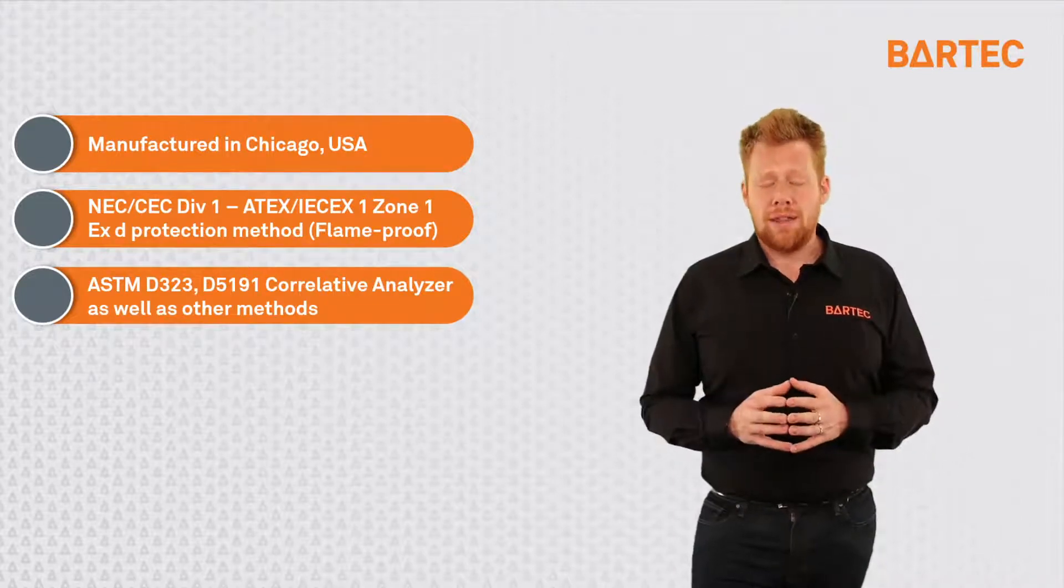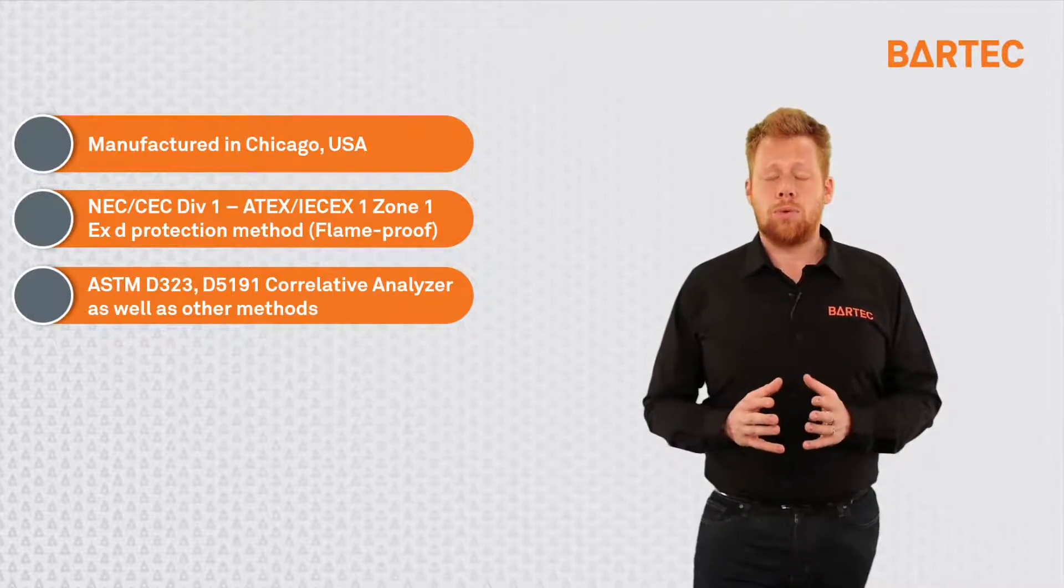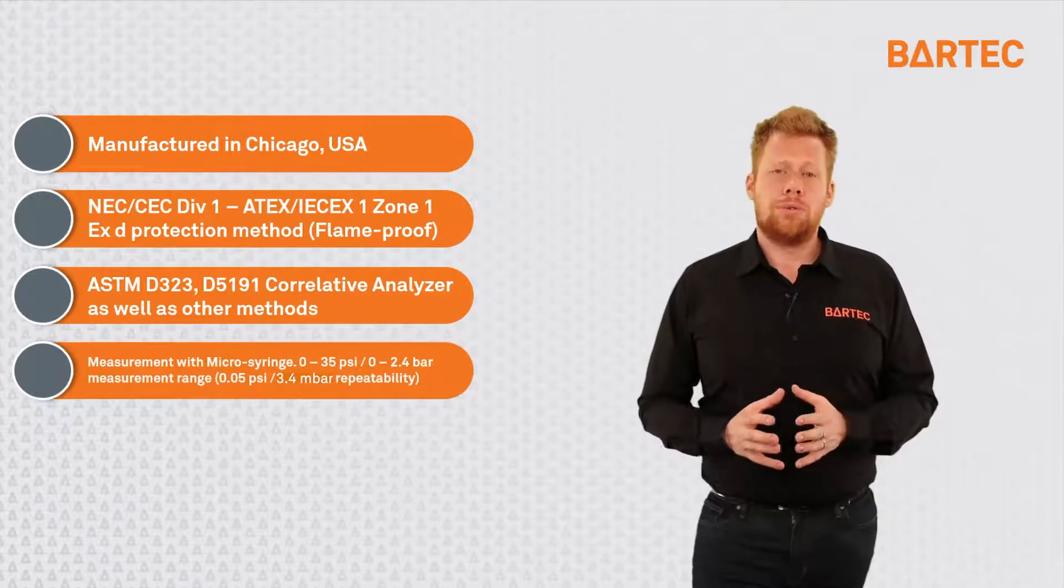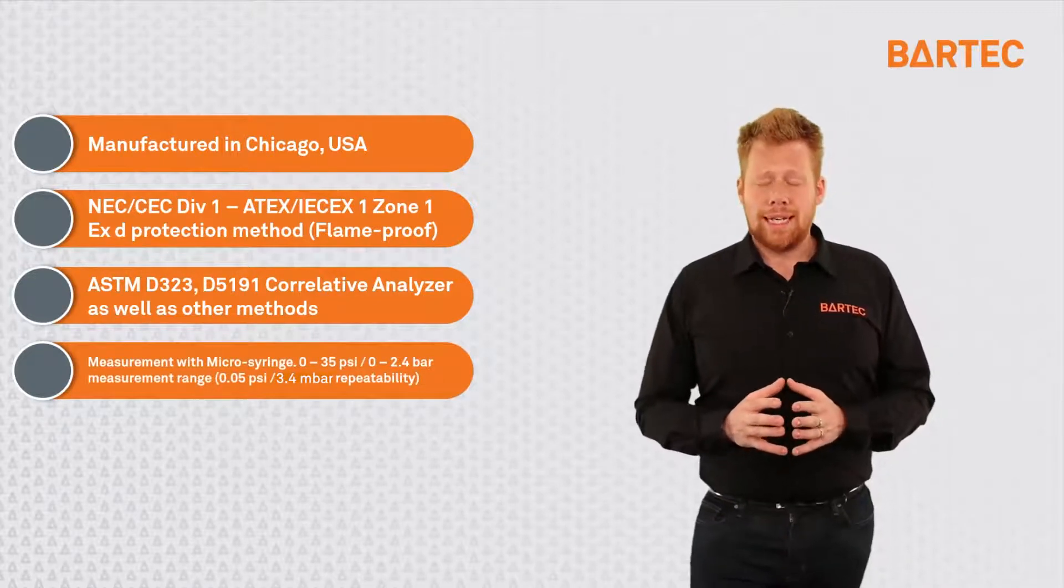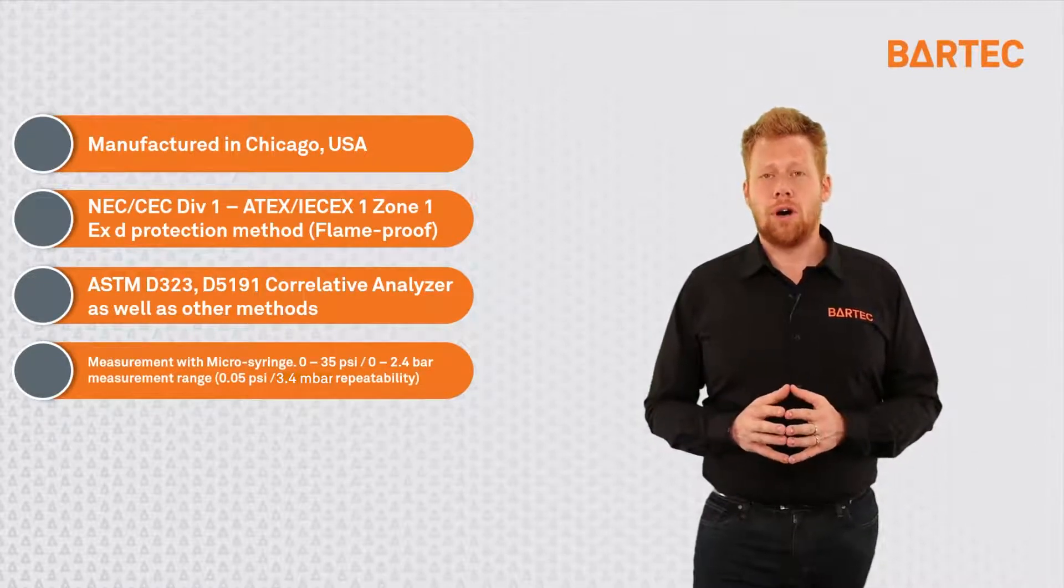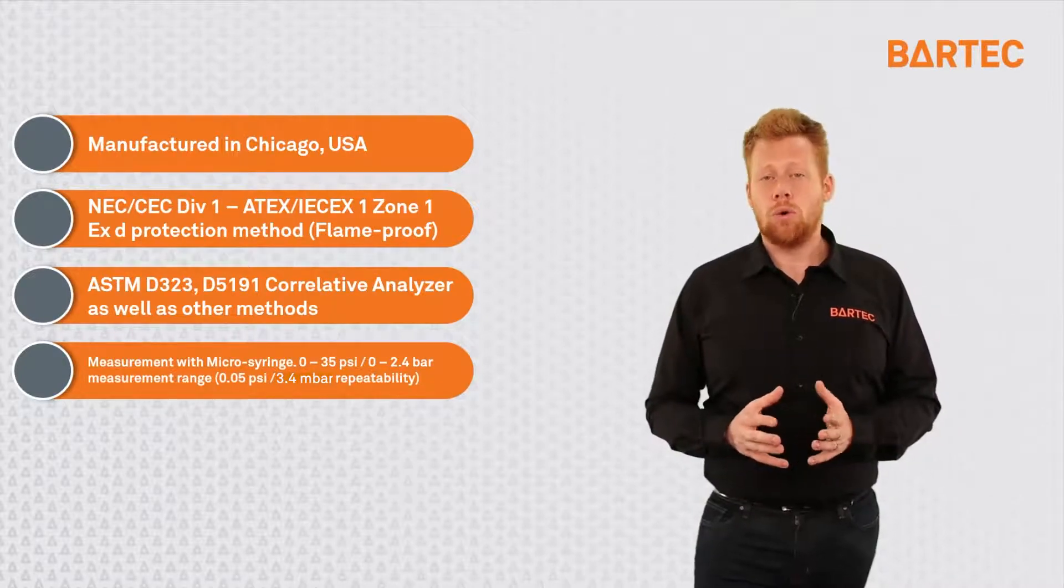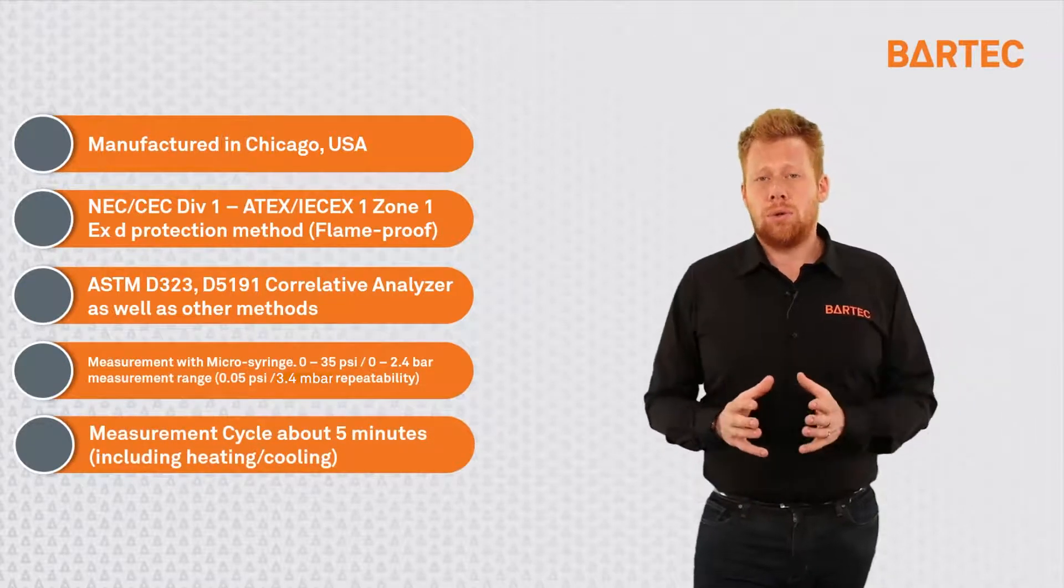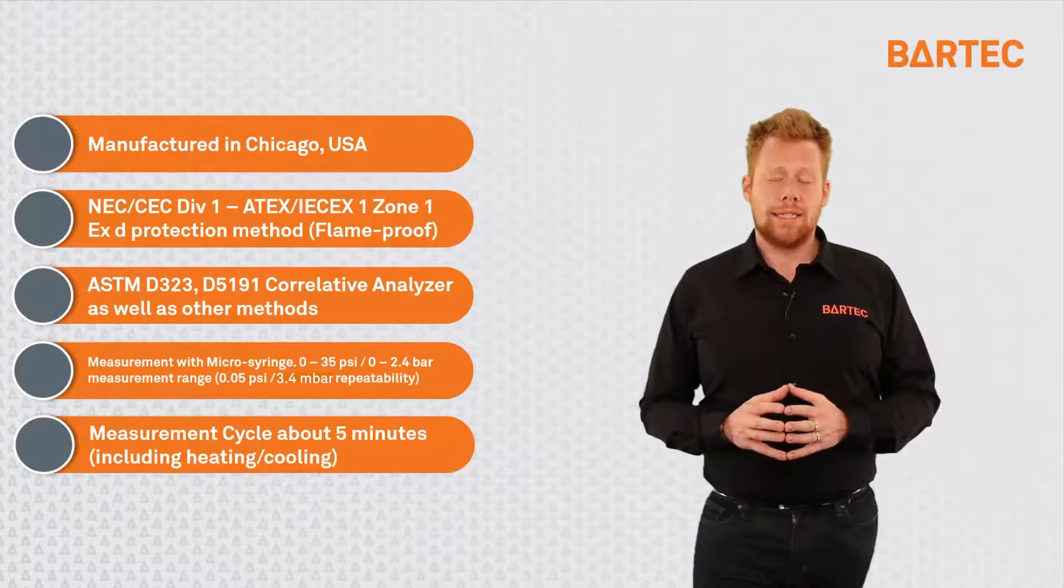The system is correlated to the ASTM D323 and D5191. We correlate to other methods, although more commonly D323 and D5191 are the ones requested. The system uses a micro syringe to do the measurement. The entire measurement range goes up to 35 psi 2.4 bars and has a repeatability of 0.05 psi or 3.4 millibars. Finally, the measurement cycle takes about five minutes in total to obtain the result. This includes heating and cooling that might be required.